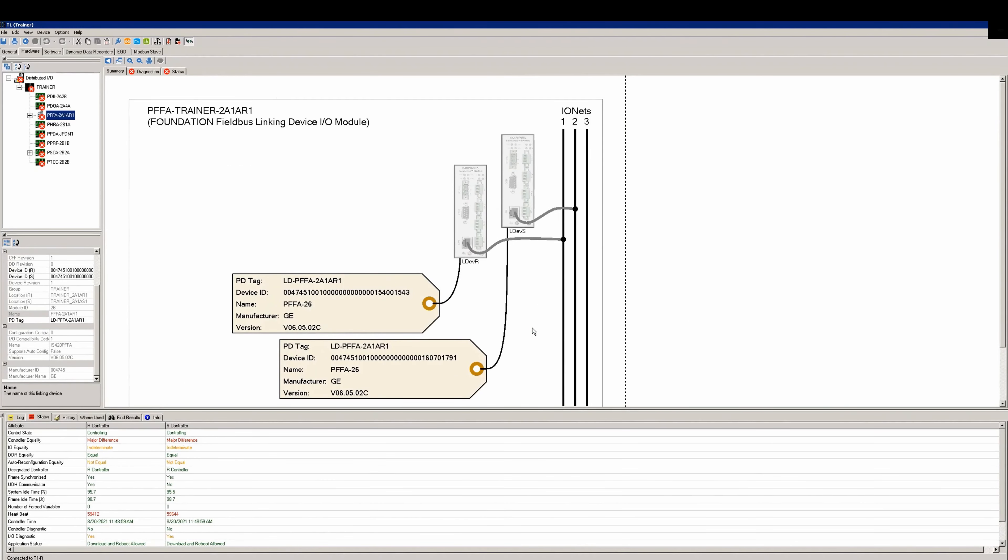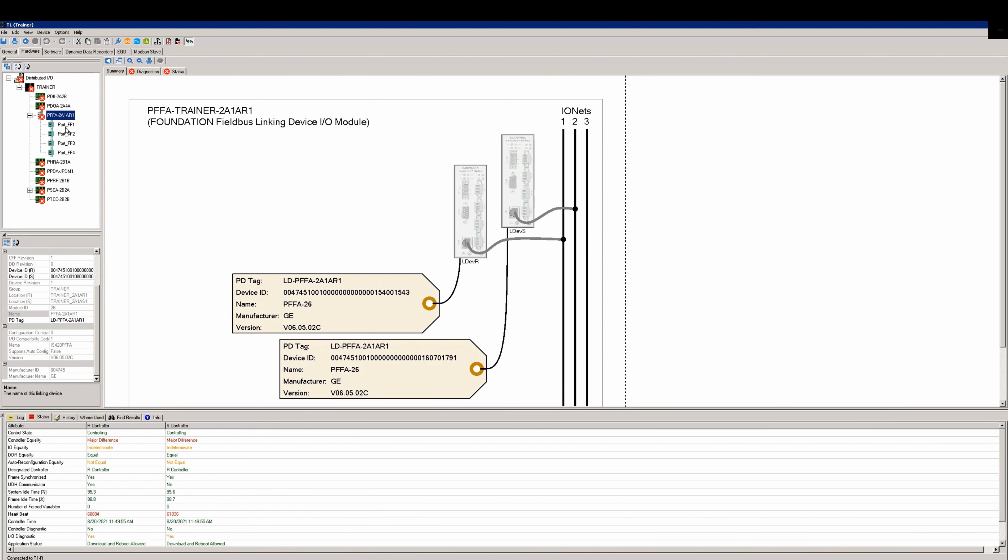You will get a warning telling you that since you're adding the first pack of its type, a reboot will be required on the next download. This only occurs for the first and last pack added. You'll see that all the IO now goes red and in error due to the major difference you've created by adding the pack.